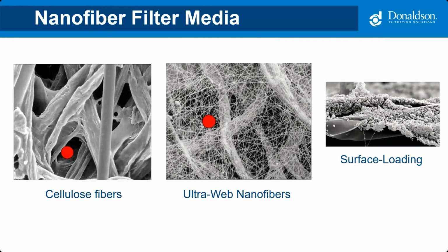However, dust cannot easily get in beyond the surface of the ultraweb nanofiber in the image in the middle. This allows for surface loading of the filter media, which improves filtration and cleaning efficiency. It's a lot easier to pulse fine dust off the surface of the media rather than from deep inside.